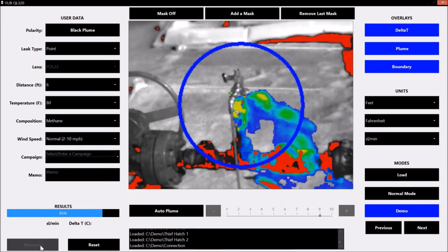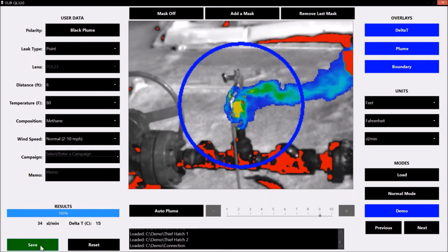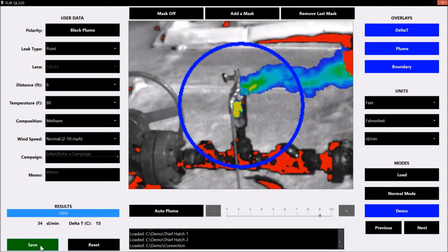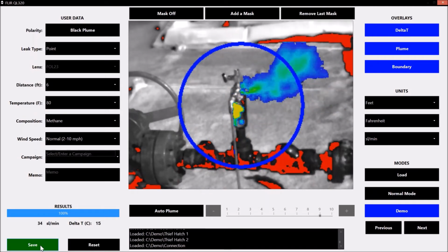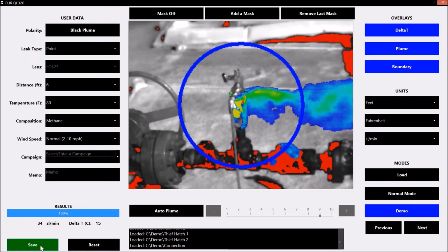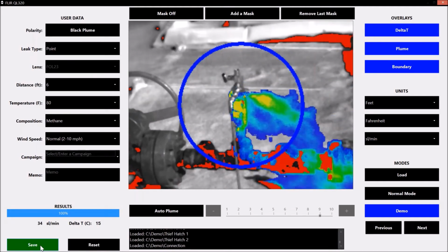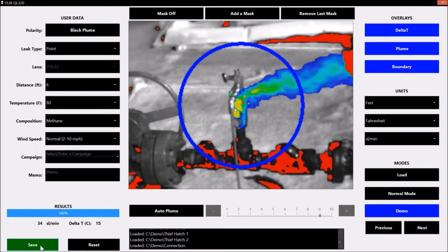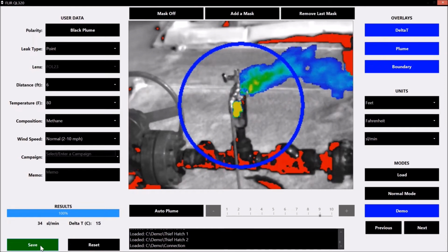This is not the actual accurate temperature. But I'm manipulating the QL320, so now you're going to have more interference on the piping itself, and it's going to change the algorithm also because I'm changing the intensity of the delta T in the background versus the ambient air temperature that I'm putting in.